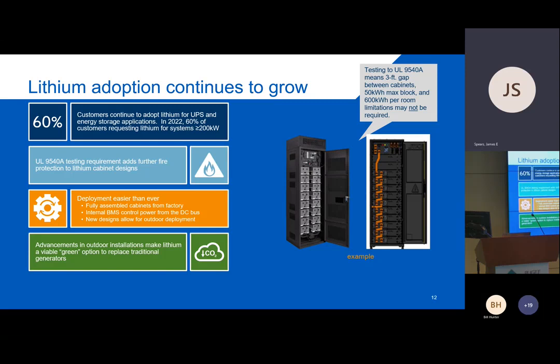So those are two things that are changing now with more modern lithium cabinets. Nowadays, a new lithium cabinet will run with internal power from its own battery rather than requiring an external AC source. Most of the new lithium solutions out there, the one on the right is an example, ship complete, not with the bus bars that link the battery modules together, but with all the battery modules installed, all the control wiring installed, et cetera. So it's a very quick process to literally install and commission that battery once it gets on site. Those are two of the things that have helped to increase the acceptance rate, especially in very recent years.